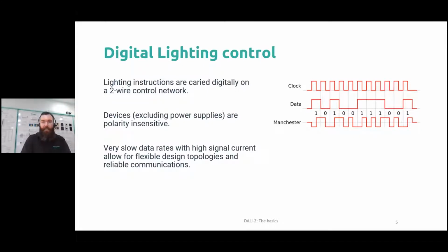When you've got a standardized and digital system, all of that is offloaded to these devices, which makes that much easier. The other advantage is that the DALI system in particular uses a very slow data rate with a very high current. So in a lot of installations, that current is certainly a minimum of 50 milliamps up to, I suppose, a more typical 230, 250 milliamps, which is almost an order of magnitude higher than the majority of your digital systems.